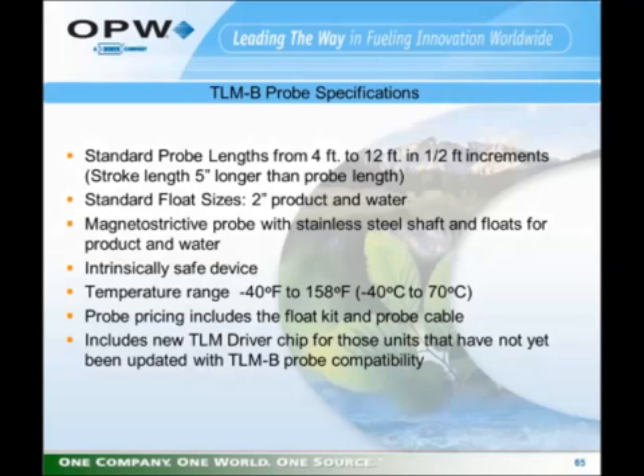Standard float sizes are 2-inch product and water, stainless steel shaft, and you can get stainless steel floats. It's intrinsically safe, has a temperature range of -40 degrees to 158 degrees Fahrenheit. When you purchase a probe, it includes the float kit and the probe cable. It also includes a new TLM driver chip, the version 4.3 driver chip that's required to support the TLM-B probe interface to the EECO 2000.